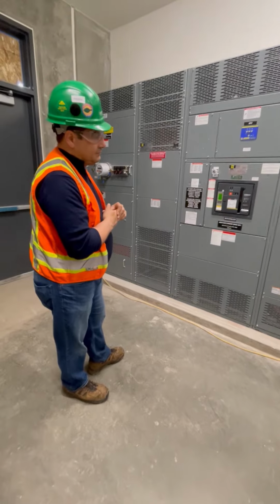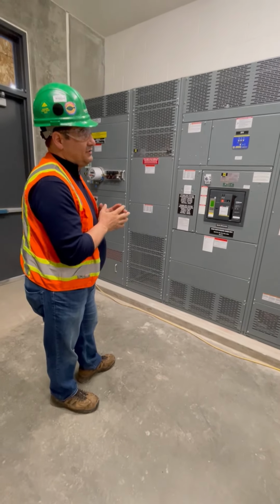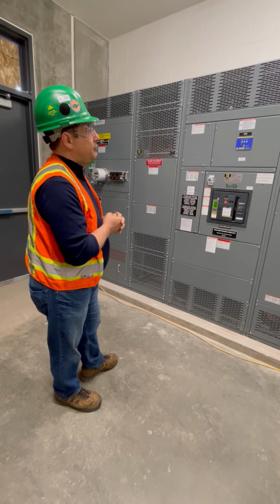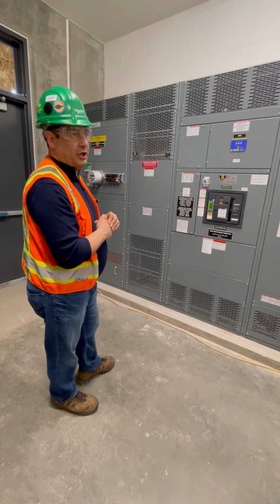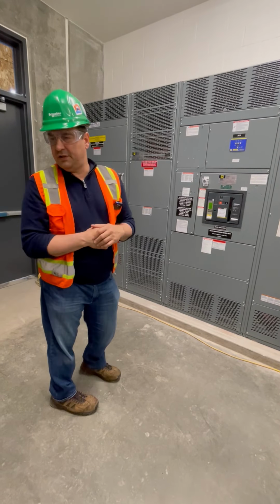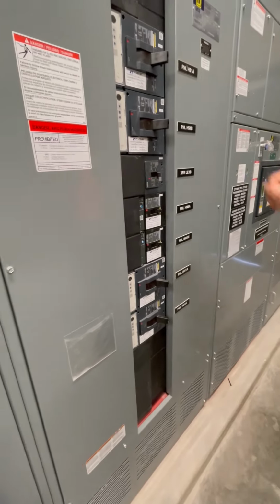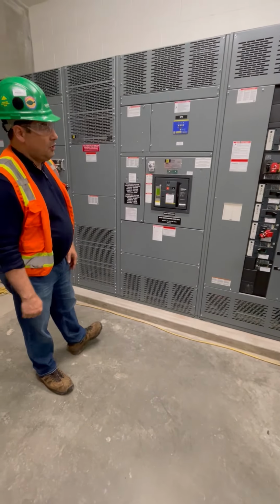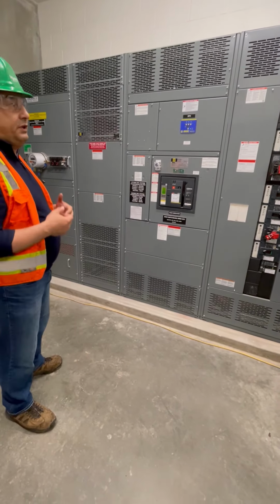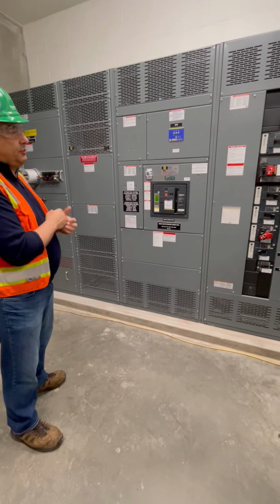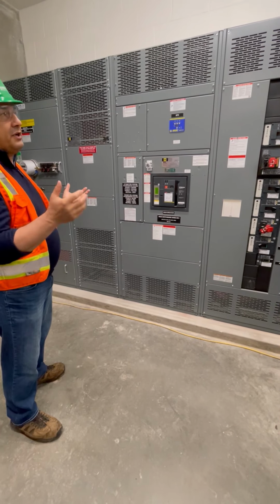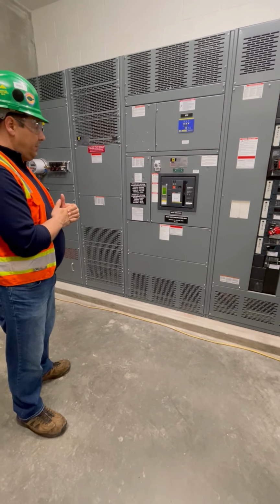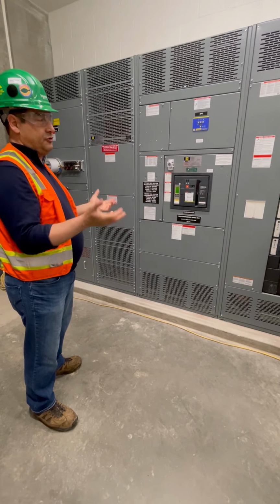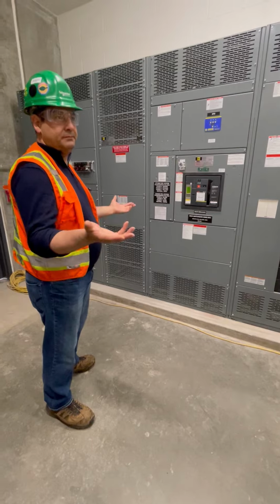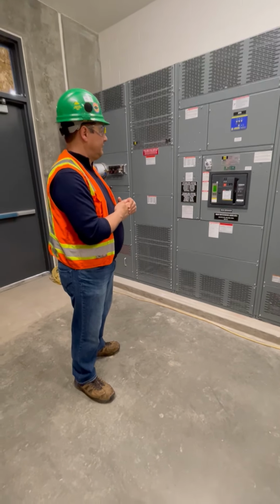Now, in the past, because the electronics were not as advanced as they are today, primary injection, if you wanted to test the breakers, was the way to go. Okay, now all of these breakers that you have here, I didn't see any thermomagnetics except two, three, a couple of them. The rest of the breakers, you can see like these here, this here, you can accomplish all that by secondary injection, which doesn't put a lot of stress on the breakers either. So in our instruction bulletin now, you will see that we recommend doing a quick secondary injection to test electronics, part of that maintenance program. If you ever want to put together a maintenance program, let us know. I'll come out, I can work with you, I can help you write that maintenance program. We can support in that direction.